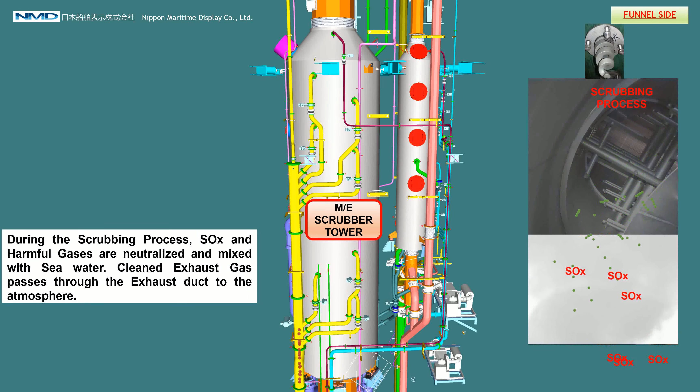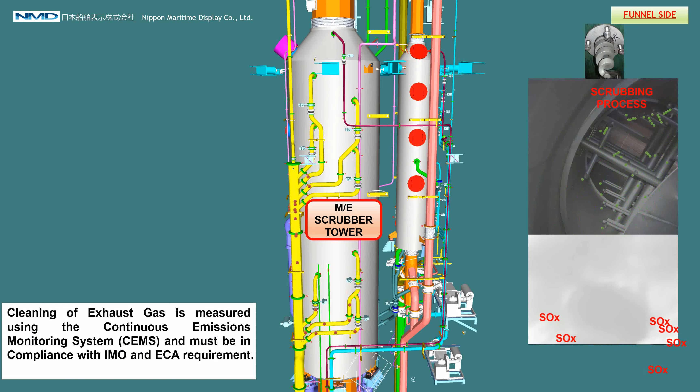During the scrubbing process, SOx and harmful gases are neutralized and mixed with sea water. Clean exhaust gas then passes through the exhaust duct to the atmosphere. Cleaning of exhaust gas is measured using the continuous emissions monitoring system, CEMS, and must be in compliance with IMO and ECA requirements.